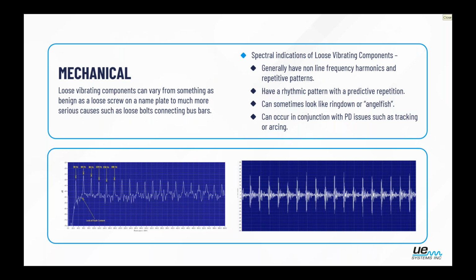And then out of all the events, probably the one that I run into more often than not when people are not sure what they're listening to is a mechanical issue. And that could be everything from very benign, the nameplate on the cabinet is vibrating because there's only 3 screws, not 4, or it could be something much more severe, like a wire rubbing on a bus bar or a bolt that's loose. There is some sort of mechanical event happening.